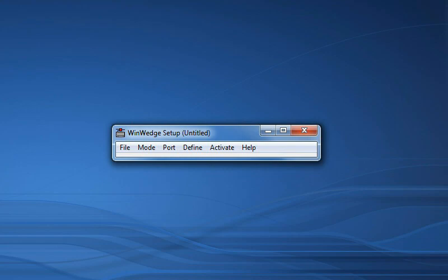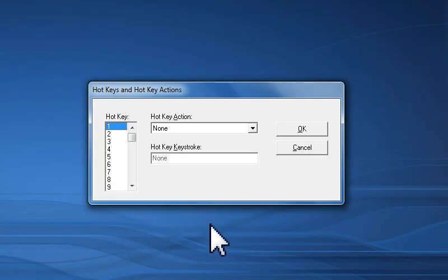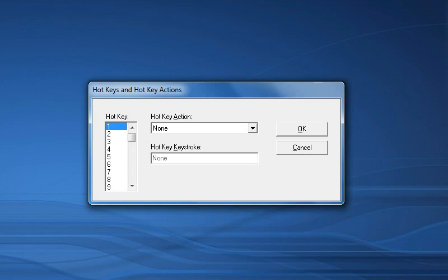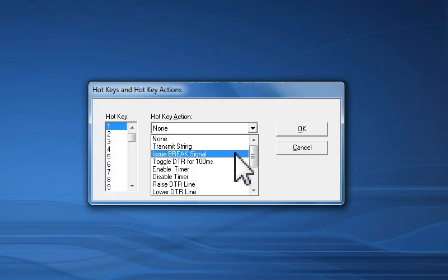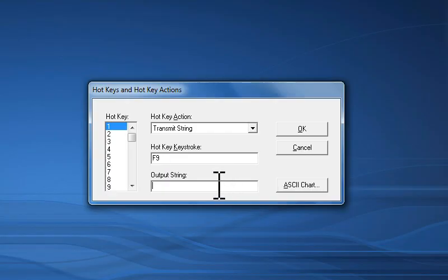Because my device requires me to send it a command to trigger it to send back a data record, I will define a hotkey that will send the required command out of the serial port to the device. To do this, I will open the Define menu and select Hotkeys and Hotkey Actions option. WinWedge will allow you to define up to 50 hotkeys that you can use to either send data out the serial port, or control the operation of WinWedge. In this example, I will define a single hotkey that transmits the question mark command out the serial port whenever I press F9 on my keyboard. For the hotkey action, I will select Transmit String, and then put my cursor in the hotkey keystroke text box and press F9 on my keyboard. Finally, I will type in the question mark in the Output String text box and click the OK button to return to the main menu.